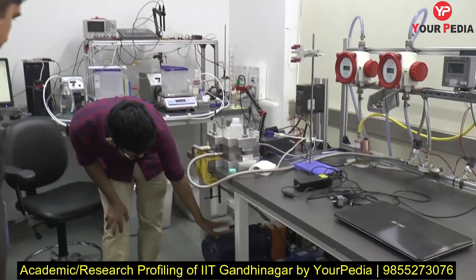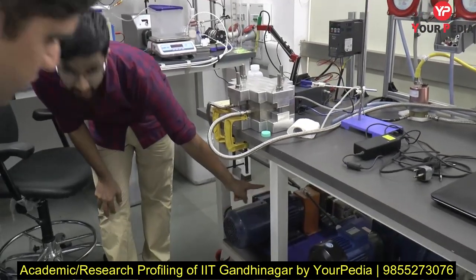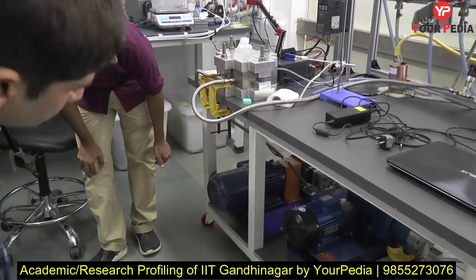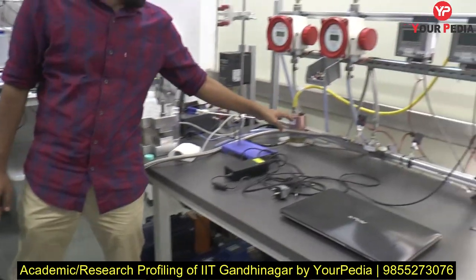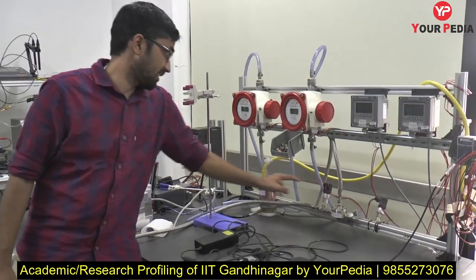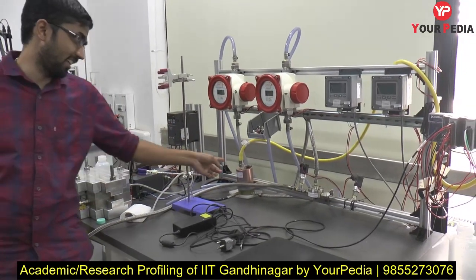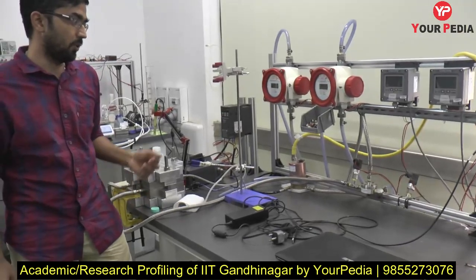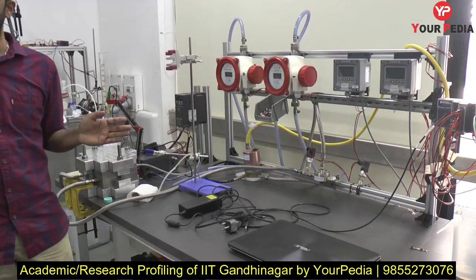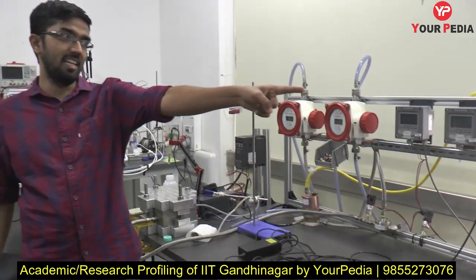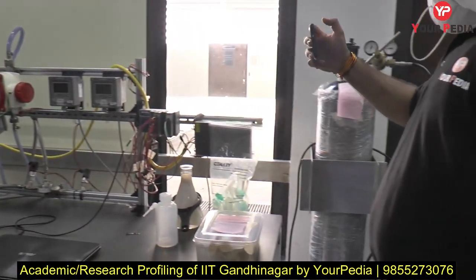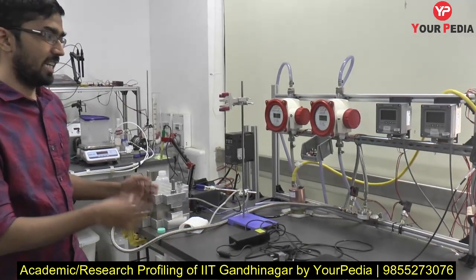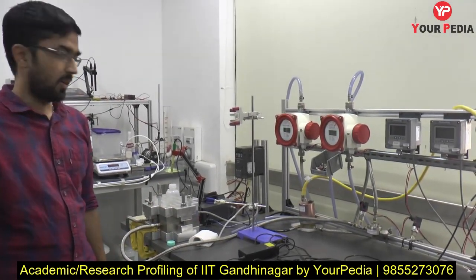So how do we generate that high pressure? The high pressure is generated by this motor, which is connected to a high pressure pump at the bottom. The pressure level is set using this back pressure regulator. The back pressure regulator is controlled by this device, to which we can supply an electric input of 4 to 20 milliamperes, and that will help us set the required pressure. The pressure finally is coming from that high pressure nitrogen tank. We also have instrumentation to measure flow rate and pressure at different locations. That's broadly the idea.